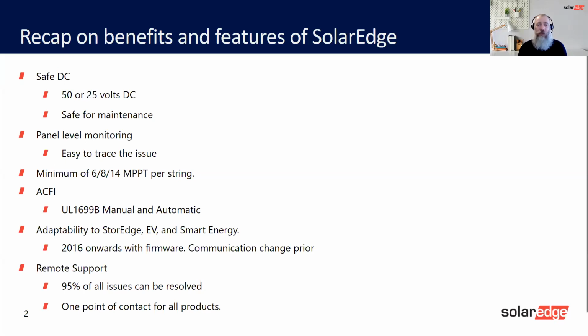So we have arc-fault circuit interrupter. This detects an arc, a parallel arc or a series arc. And then using the safe DC, we then turn off the optimizers. We stop the optimizers from letting the voltage through and reduce the current to below 300 milliamps. This then reduces the arc, because the arc is basically a jump between two conductive pieces of equipment through air. So that reduces the current and therefore stops the arc.